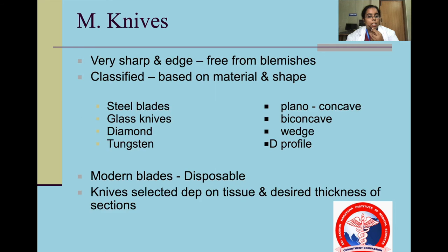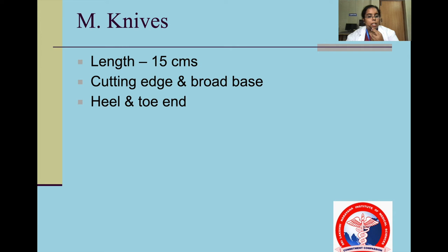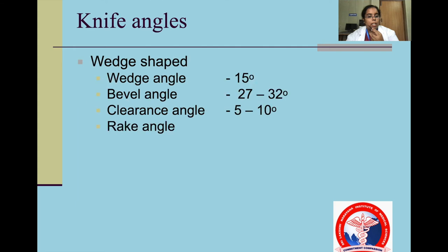The knife should be very sharp and the edge free from blemishes. Steel blades have planoconcave, biconcave, wedge and D profiles. Other blade types include glass, diamond and tungsten; modern blades used nowadays are disposable. Knife length is initially 15 cm with a cutting edge and broad base. The two ends of a knife are the heel and the toe. The wedge-shape knife has a wedge angle of 15 degrees, bevel angle ideally 27 to 32 degrees, and clearance angle usually 5 to 10 degrees. You should also know the rake angle.